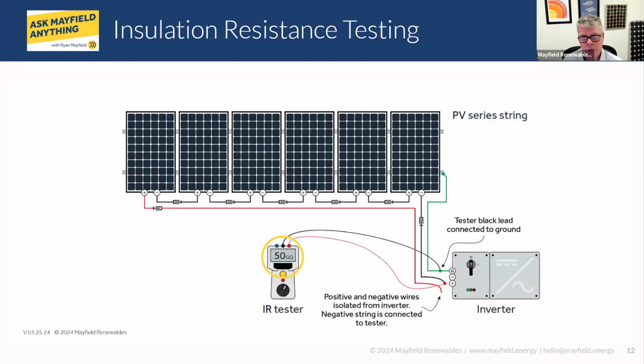The IEC standard I referenced has some voltage values that they recommend testing at, but specific to PV systems, you should never do this test where you induce a voltage that's greater than what the modules are rated for. So if you are testing modules that are only rated at 1,000 volts, do not test above 1,000 volts. If you're doing older systems that are only 600 volts, that's going to be your limitation. Understanding what you're working with is really important. Thanks for pointing that out, because that is a really critical part of this entire test.